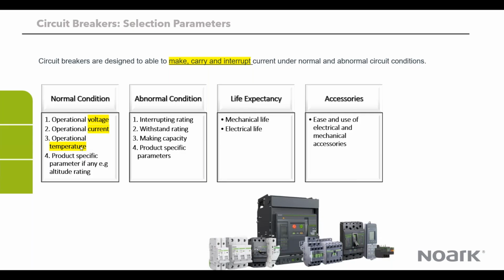You make sure that the specific circuit breaker you're selecting has the correct rating. Same with the rated current, which is a function of the load requirement. What's the summation of the load requirement for that facility or for that system? That guides you on what the operational current, or what the rated current, should be.